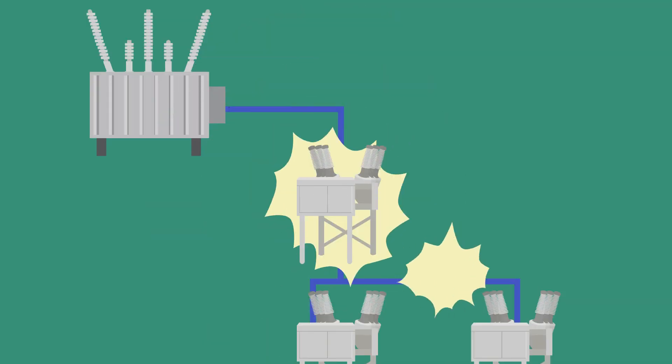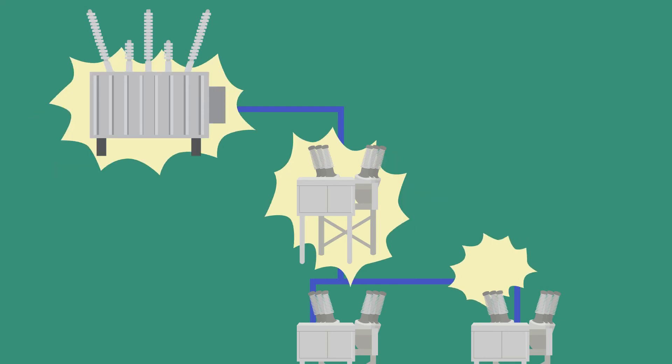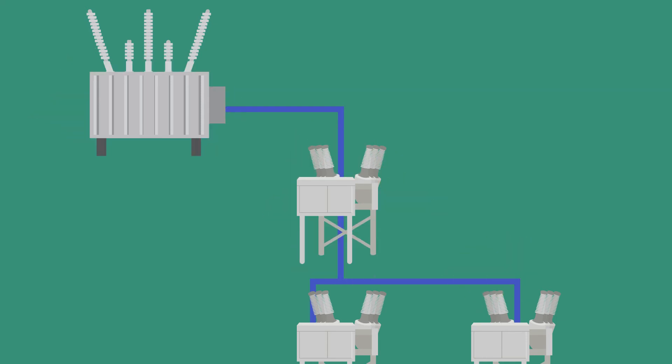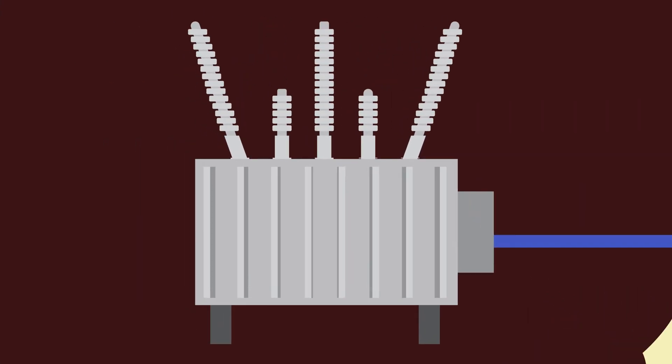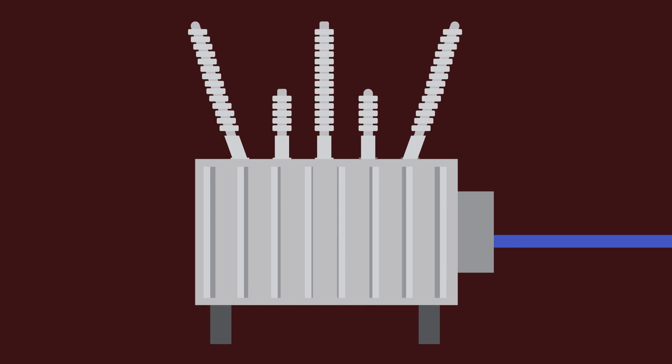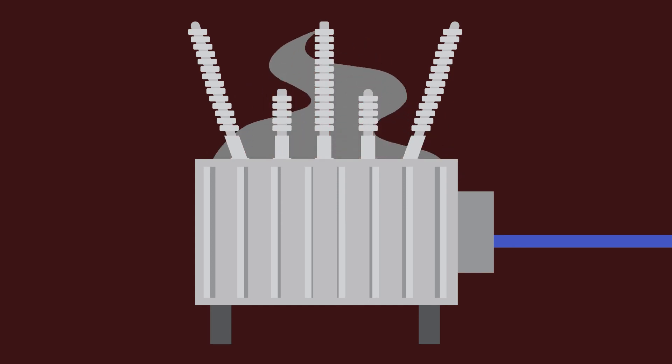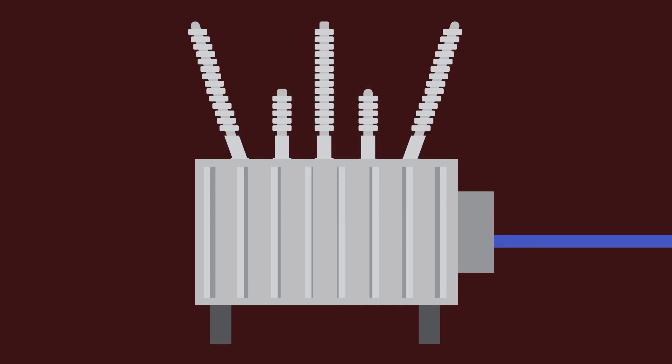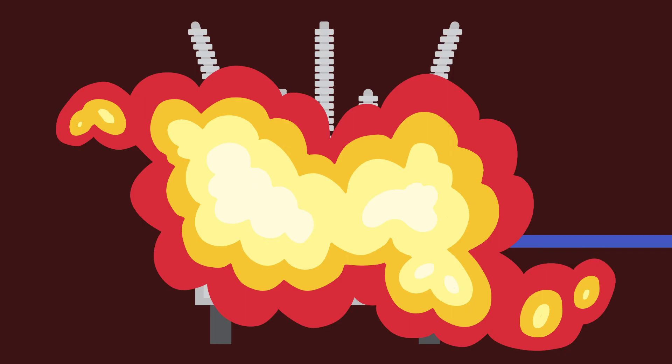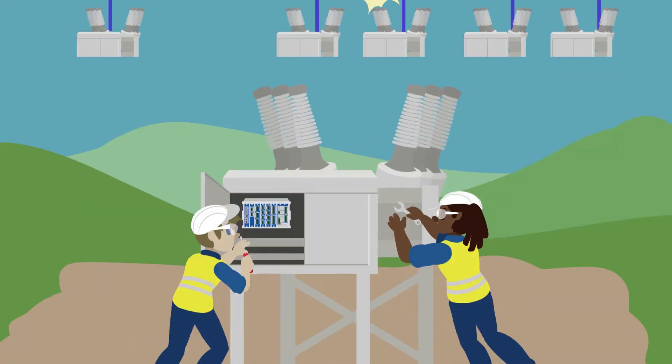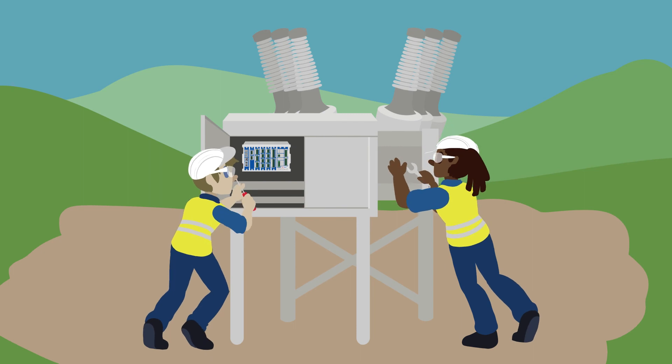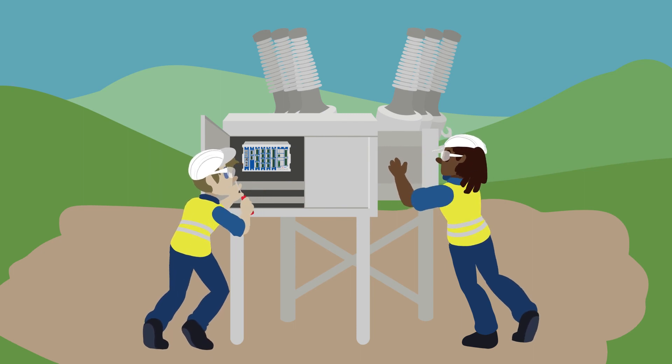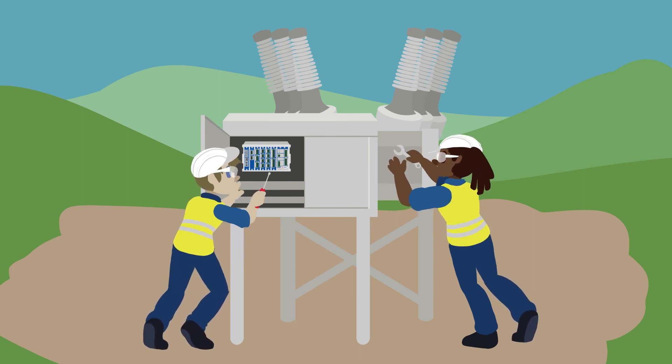If a breaker fails to operate properly, fault currents go uninterrupted and an excessive amount of current is induced within the transformer's windings. This results in premature aging of the transformer and can possibly lead to catastrophic failure. Since fault interruption depends on breaker performance, breakers must be consistently maintained to ensure they operate within their specified parameters.